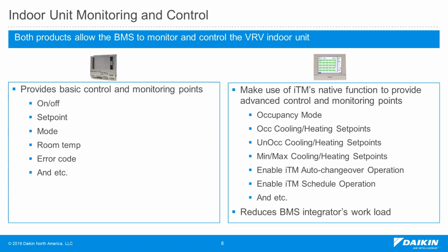mode. On the other hand, if you are using the hardware gateway, the BMS integrator will need to write their own program for the occupancy mode, and the different set point depends on the occupancy. So similarly, the BMS can enable ITM's auto changeover logic, and also the ITM's own schedule function. So by using the ITM BACnet server gateway function, you can significantly reduce BMS integrators' workload, and the learning curve for the integrators to learn how to control the VRV system can be reduced as well, and it can prevent potential misunderstanding or controlling problems.